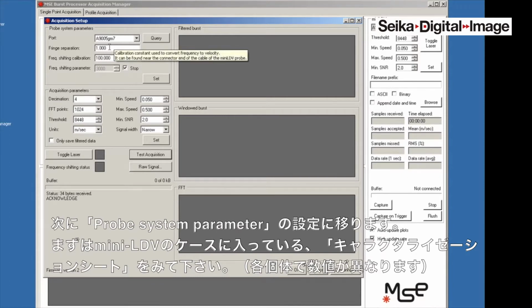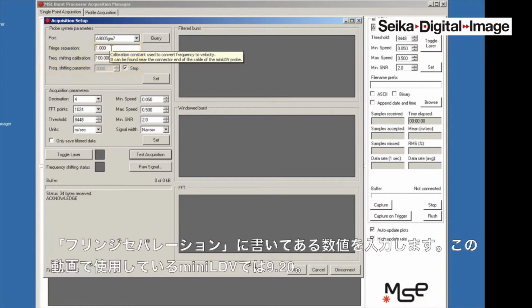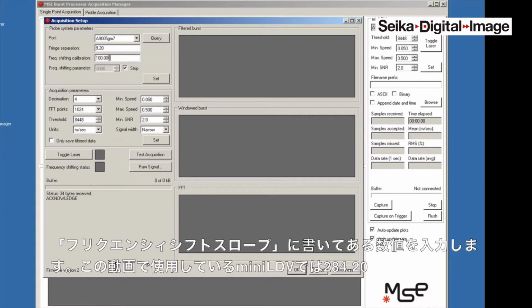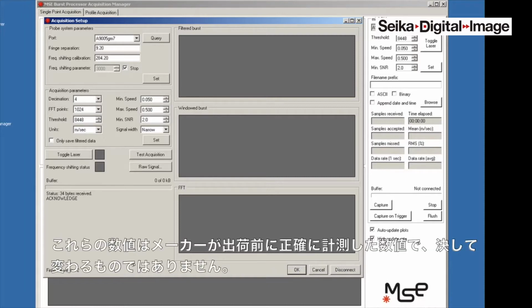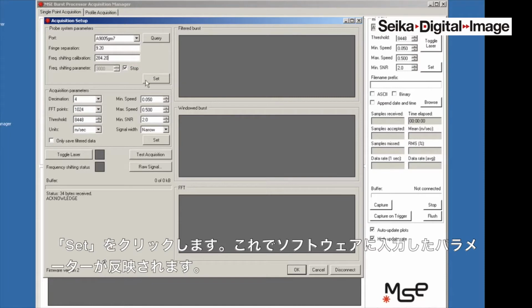The first thing you need to do is to look at the characterization sheet that is provided with your miniLDV and input the correct values here for the fringe separation. In this case, the one that I'm using is 9.2 microns. And then there is an item called frequency shift slope, which is the fringe frequency shifting calibration number, and in my case it is 284.20. These two numbers were measured or set in the lab and never change for the life of the probe itself. Once you do that, push set so that the software acknowledges the receipt of these parameters.